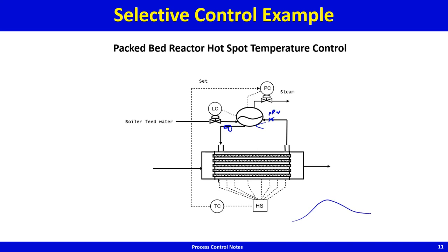The heated water is then depressurized and flashes, so the heat removed from the reactor leaves the system as steam. The typical temperature profile in such cooled packed-bed reactors shows a hot spot that is not stationary — it moves up and down. To track it, a bunch of temperature sensors are placed across the reactor length, and a high selector picks the highest temperature reading.